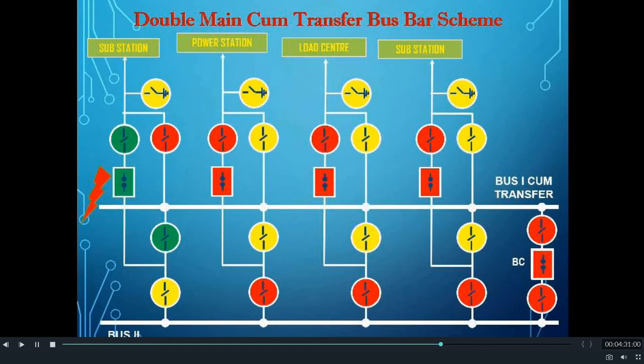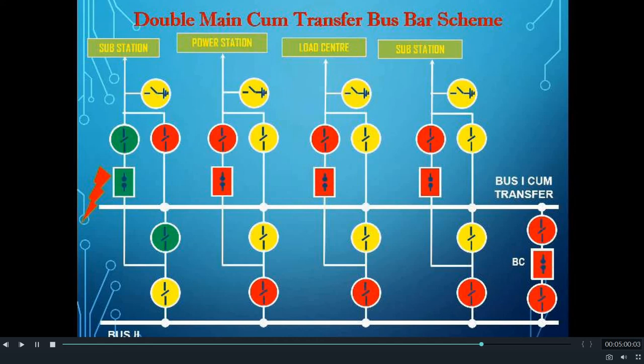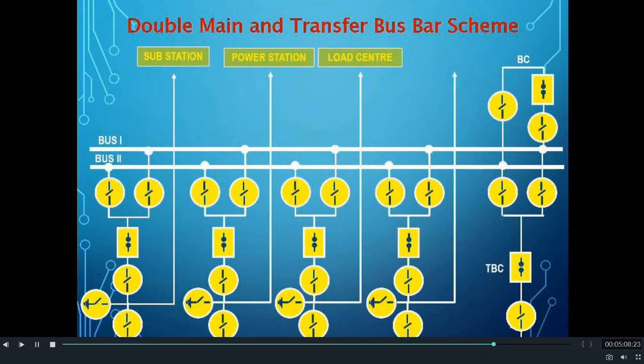By using this bus bar scheme, in case of a bus bar fault, all the feeders can be kept in service by connecting all feeders to the other bus bar. Also, in case of any circuit breaker fault, the feeders may connect to the system through the bus coupler. However, the main drawback of this system is that both types of faults cannot be accommodated together — that is, in case of both a bus fault and a circuit breaker fault simultaneously, some of the feeders will be out of service.